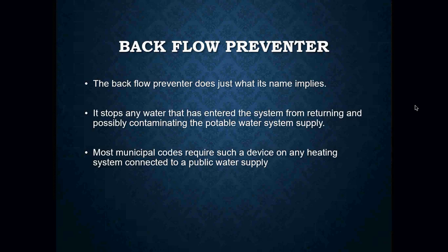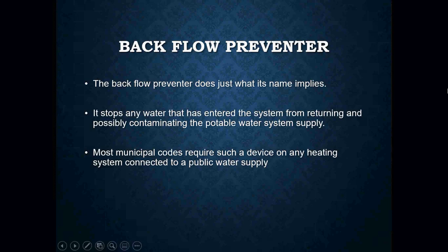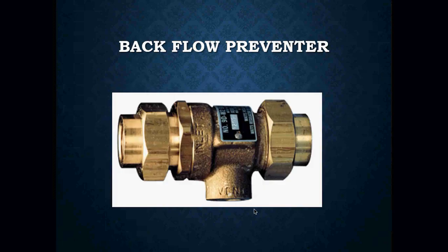The backflow preventer does exactly what the name implies — it prevents water from back-flowing. It stops water entering the system from returning and possibly contaminating potable water or the potable water supply system. Most municipal codes require such a device on any heating system connected to a public water supply. They must be installed in the direction of water flow — there is an arrow stamped on the brass.